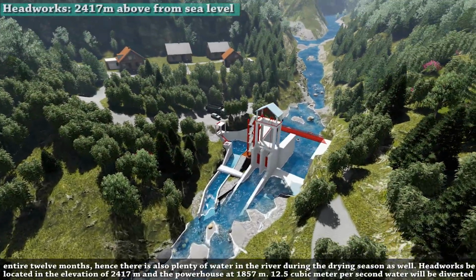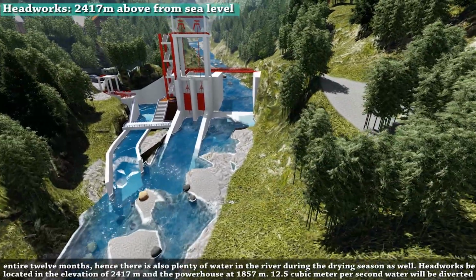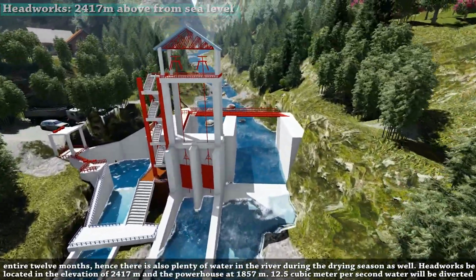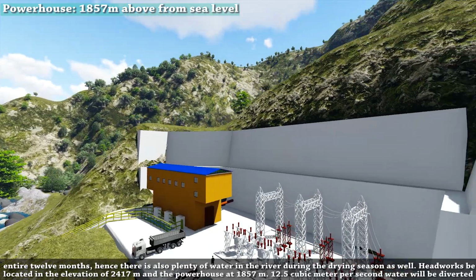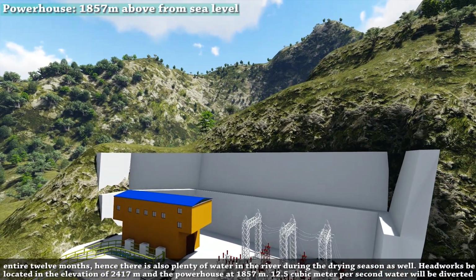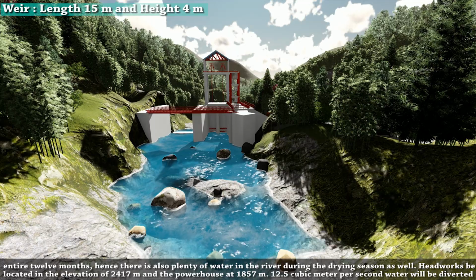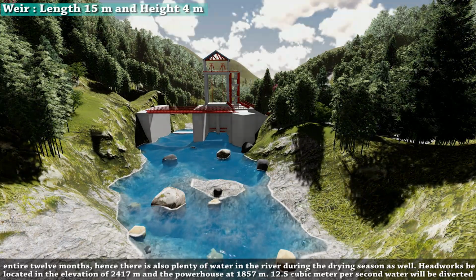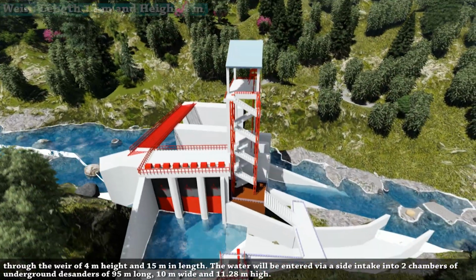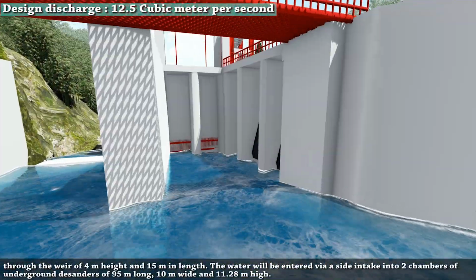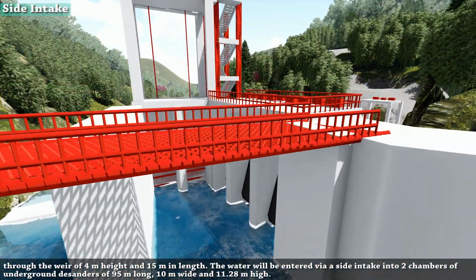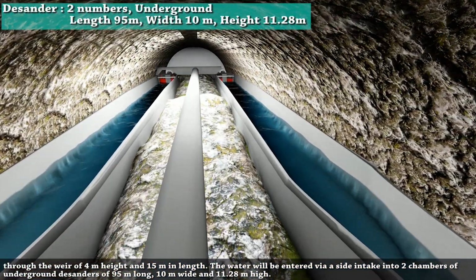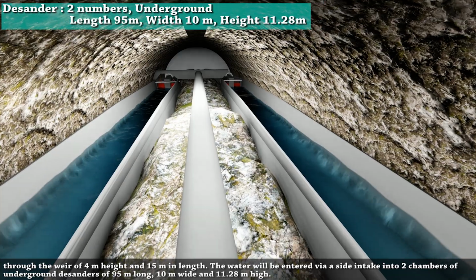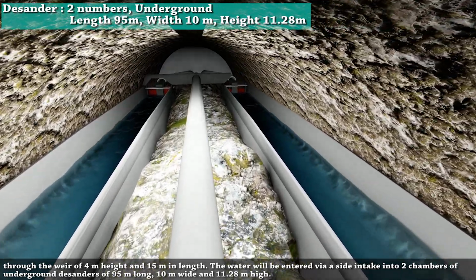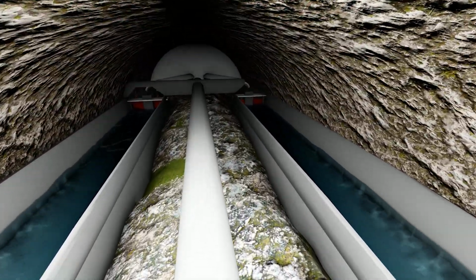The headworks will be located at an elevation of 2,417 meters and the powerhouse at 1,857 meters. 12.5 cubic meters of water per second will be diverted through a weir 4 meters high and 15 meters in length. The water will enter via a side intake into two chambers of underground desanders, 95 meters long, 10 meters wide, and 11.28 meters high.